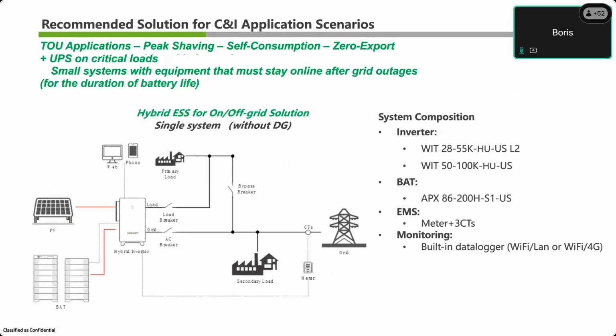This is what the system looks like when you add a backup load. So you can separate your loads, or you can put all of your loads on the primary load. As we have it shown, we have a primary load and a secondary load. The secondary load will not have battery backup, but the primary load would, because it's on the load port of the inverter. So in the event of a grid outage, our inverter has an internal ATS at the grid input, which will open. And so the secondary load will not have power, but the primary load will. The last thing that's noteworthy on this diagram, besides the overall system and how simple it is, is the bypass breaker. We have a bypass breaker in there just for maintenance. So if you want to do some work on the inverter, but you need your load to stay online, then you can use that bypass breaker to keep the system online over grid. But that's its only function.